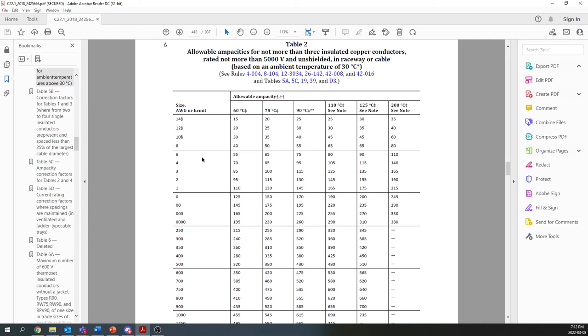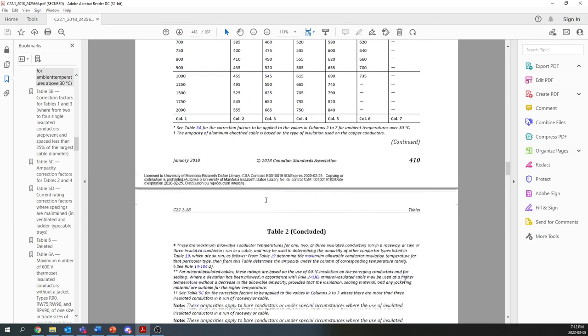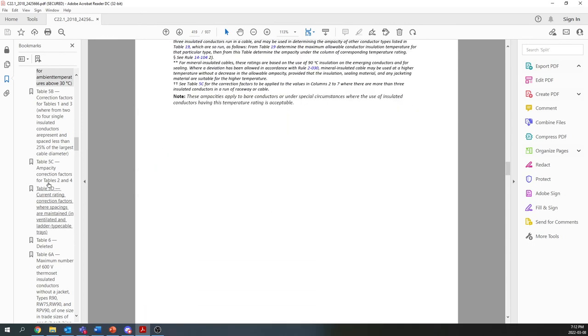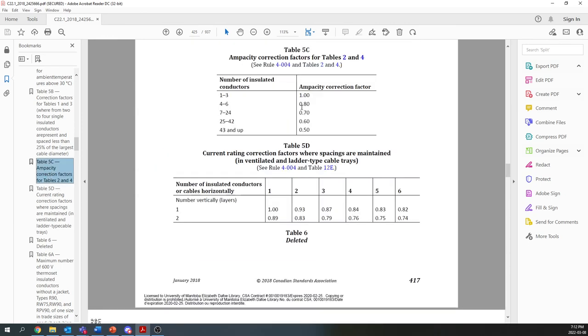In any case, now we know we have 2 number 6 wires and 3 number 4 wires. What's next? Now we have to look at the correction factors for the number of insulated conductors in Tables 2 and 4. Oh, shoot. Now we have another ampacity correction factor. So we know we have 5 insulated conductors in our wire.